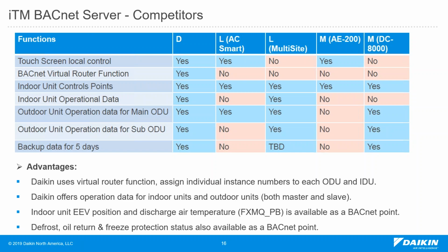Indoor unit control points: all the VRF manufacturers can provide indoor unit control points. Indoor unit operation data, which is basically all the sensors, all the temperature sensors on the indoor unit, and the EEV position, we can provide that. Also the LG Multi-site. Outdoor unit operation data for the main outdoor units, we can do it. LG, yes. For sub outdoor units, our ITM can do it, and in the Multi-site, yes, as BACnet points. Backup data for 5 days, so operation data for the last 5 days, is available in our ITM. In the LG, it's not clear exactly what it is. I can see it in their engineering manual screenshot, but I didn't see any function of saving that data.